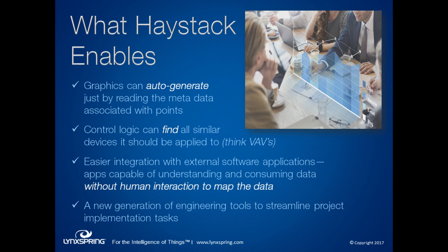But it goes beyond graphics. Even control logic can automatically find all its targets or devices. You could have a VAV control sequence that goes out and finds all things tagged as VAV boxes and applies the control logic to them — dramatically reducing the engineering effort to implement automation and control systems. When you want to integrate with other third-party applications, the fact that they can quickly understand the meaning of the data means you can implement software applications — from maintenance management, CMS, and visualization reporting — much more quickly with less effort and lower cost.